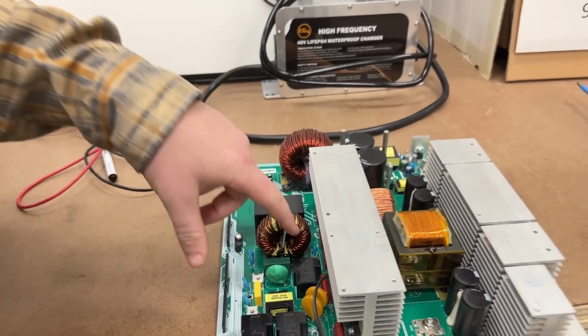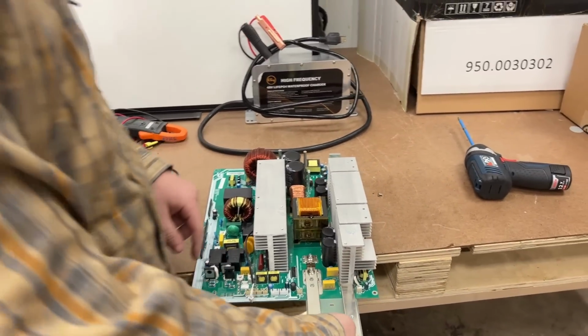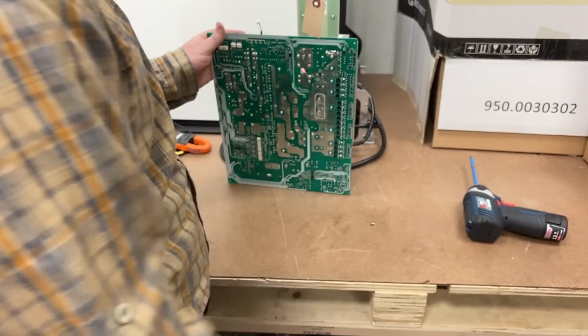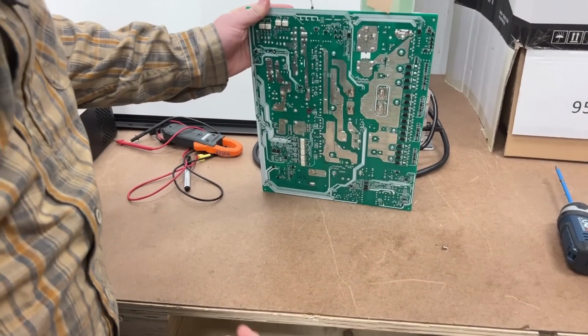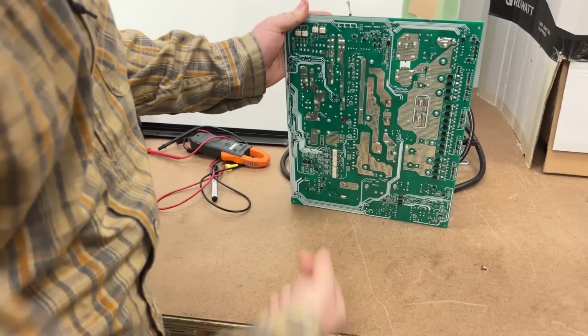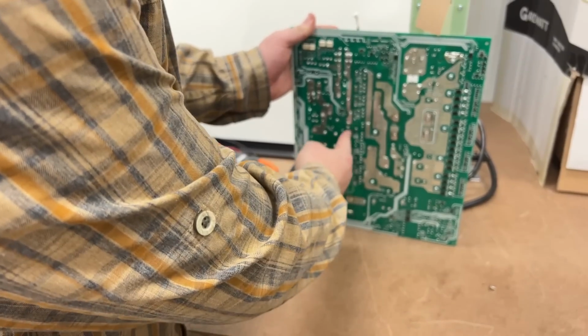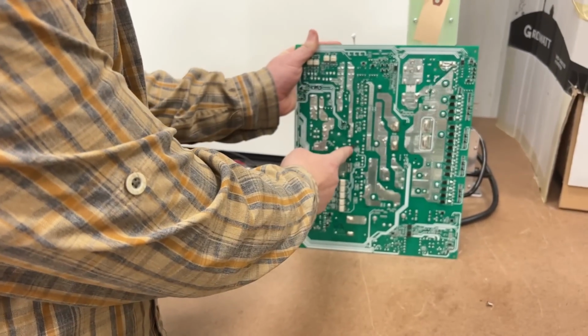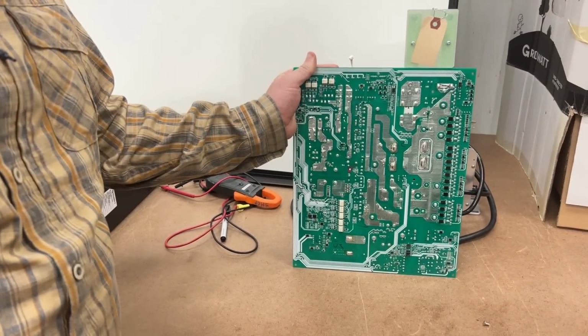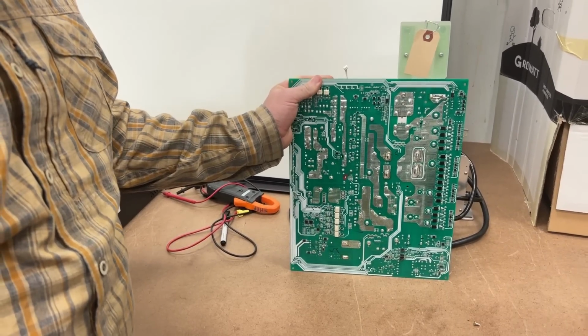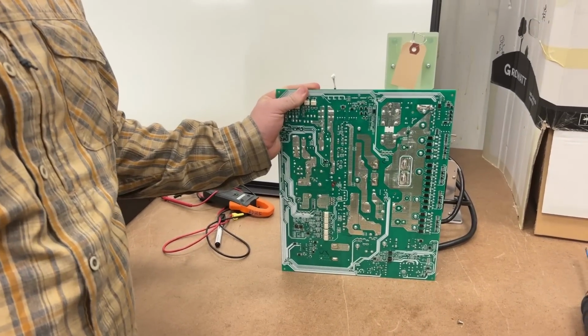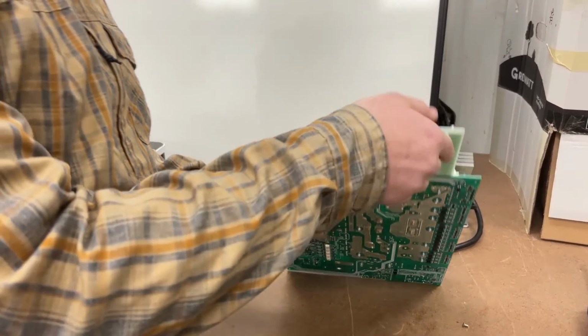And I've seen guys say, well, we removed that, and then they've said, well, there's still a contact line. Well, this is the thing about buying the right unit. When you buy the right unit from a manufacturer, they send you the right board. Right there, there is no metal contact. That is a piece of silicon. So there's no grounding. There's no leakage between ground to neutral. You truly get an unbonded unit.